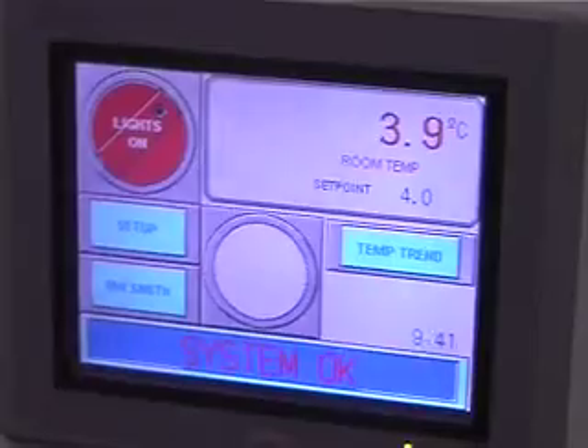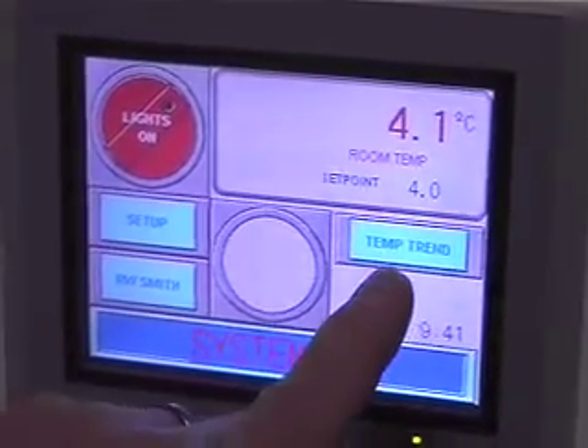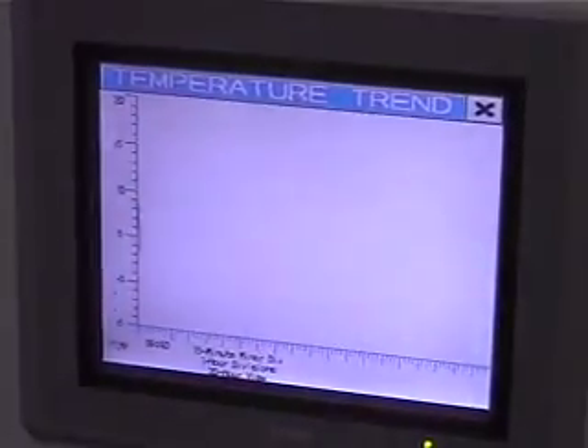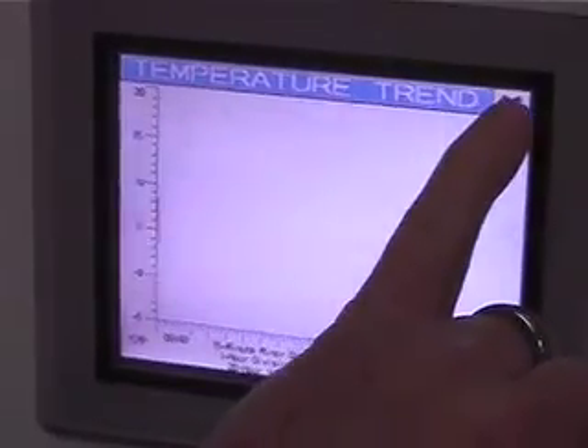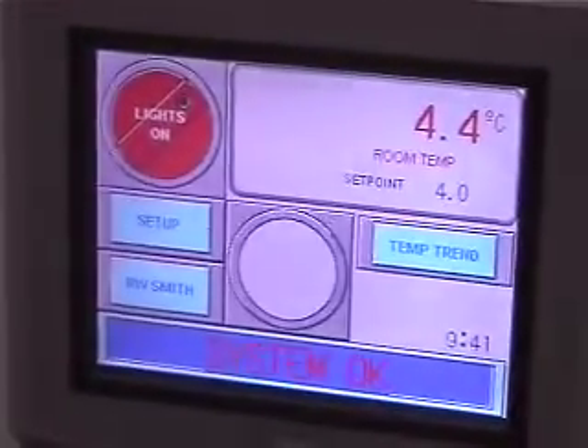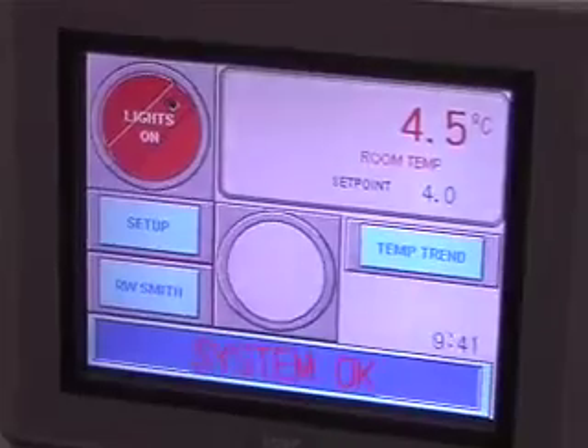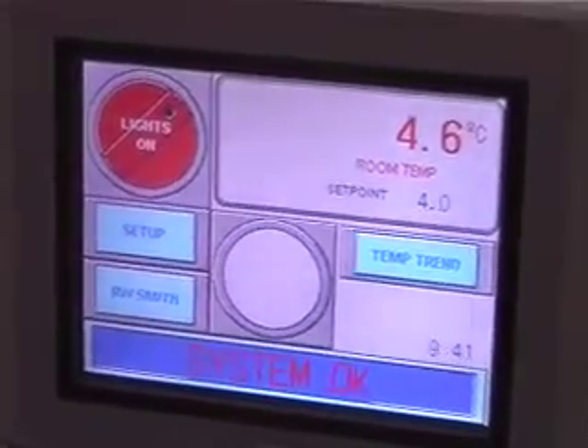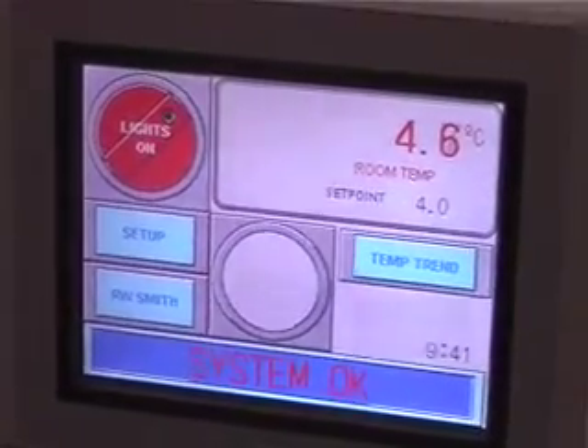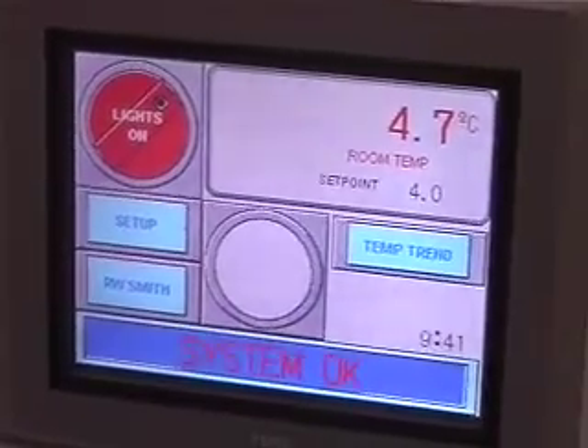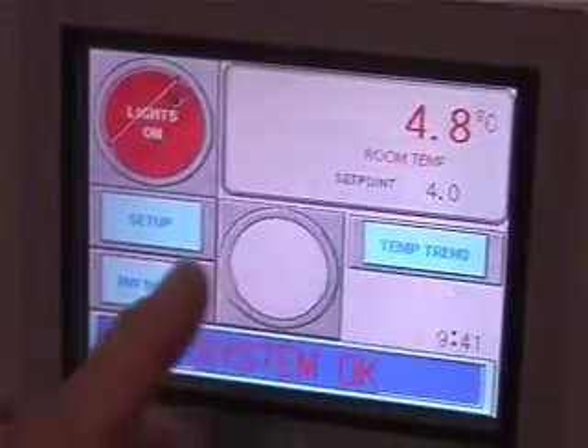Temperature trending, we don't have a chart recorder on this, so we have a temperature trend chart. Now, it's not trending yet. You had the set points on there at 4. Mm-hmm. Before you opened the door, it was down to 1. I don't know. We'll have to check it. See, we just fired it up this morning. We gassed it last night, fired it up this morning. Okay, so we'll figure it out and get that thing fixed up.